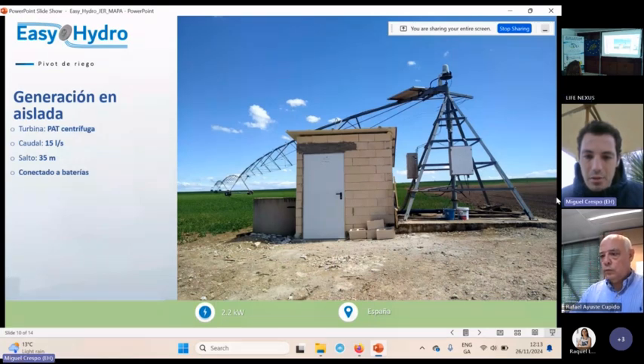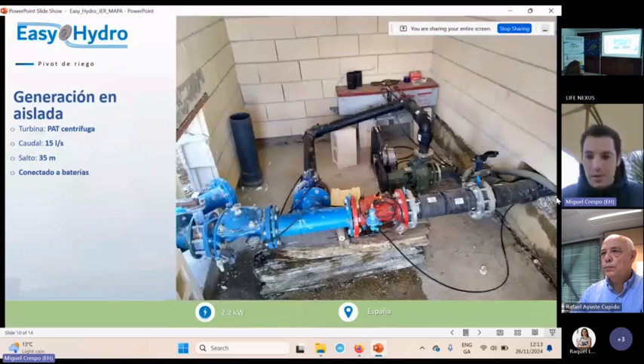It's an installation that basically takes the water before entering into the irrigation pivot. We had around 50 liters per second and 35 meters of net head that was being reduced by a PRV, a pressure reducing valve. The installation itself is a very rustic one, but it's what the farmer wanted.